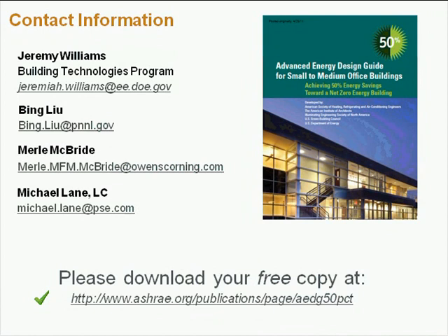The first one says, please address the application of task ambient lighting approaches and associated controls for additional energy reductions, and also address whether LED lighting options allow further wattage reductions due to superior uniformity and directionality so that illuminance is optimized on the work plane versus throughout the office. A couple of things to remember here. First of all, the guide is one way. There are going to be multiple ways to do the lighting system as long as we can get down to that 0.68 watts per square foot or the 0.75 average. And if you as a designer want to do a task ambient lighting system that uses LEDs, go for it.